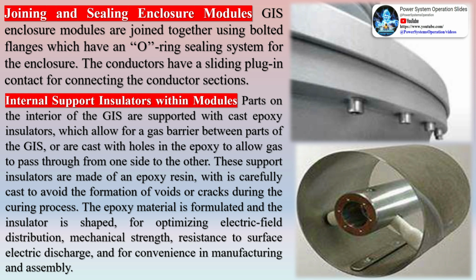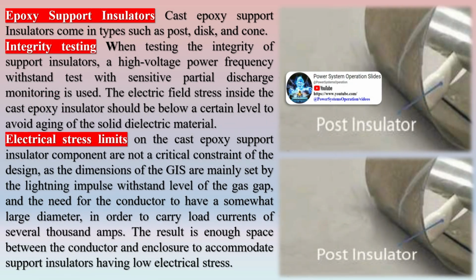GIS enclosure modules are joined together using bolted flanges which have an O-ring sealing system for the enclosure. The conductors have a sliding plug-in contact for connecting the conductor sections. Cast epoxy support insulators come in types such as post, disc, and cone. Integrity testing. When testing the integrity of support insulators, a high voltage power frequency withstand test with sensitive partial discharge monitoring is used. The electric field stress inside the cast epoxy insulator should be below a certain level to avoid aging of the solid dielectric material.